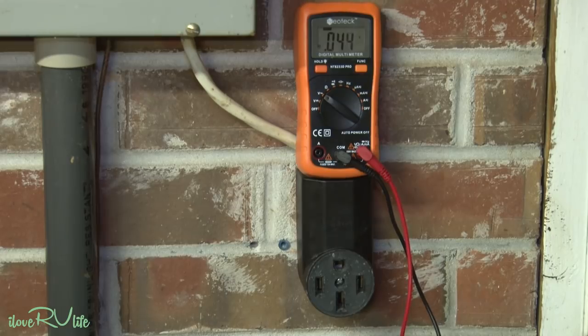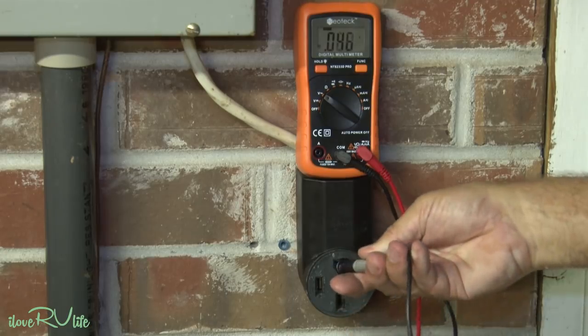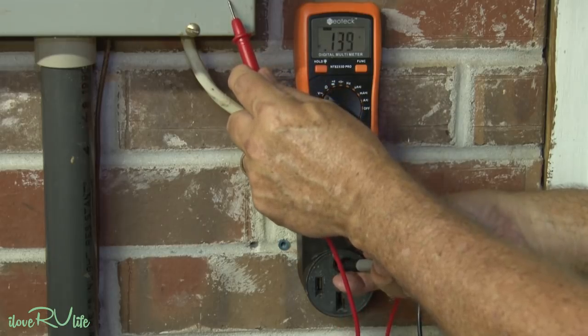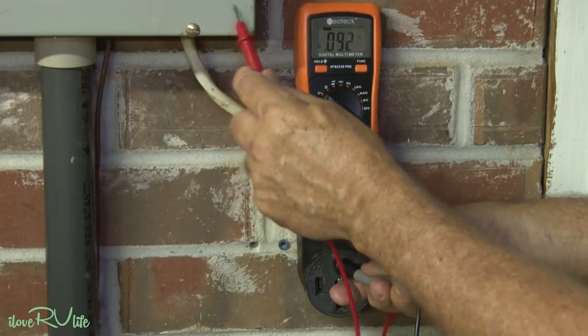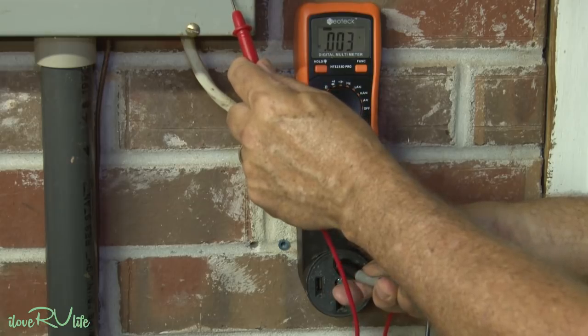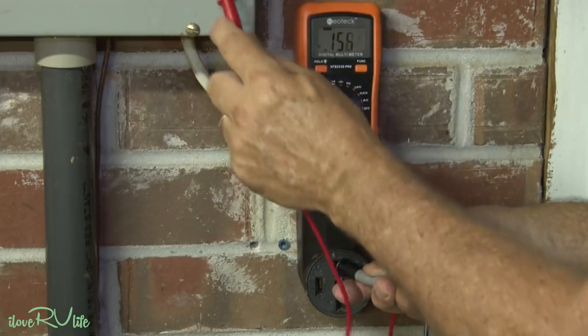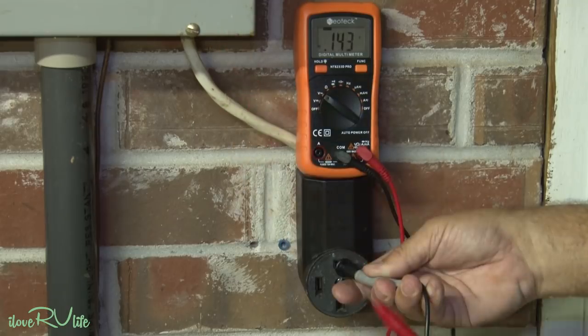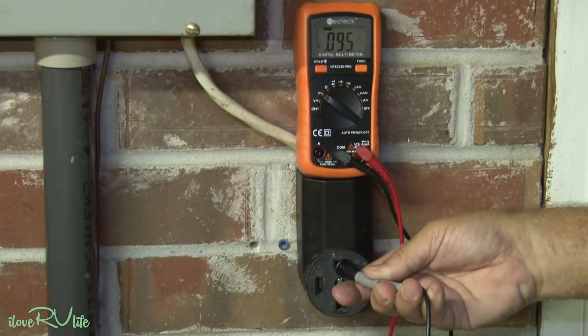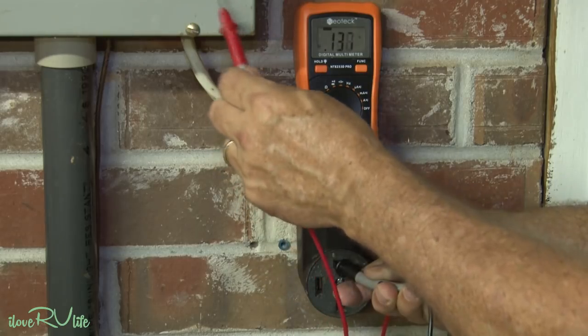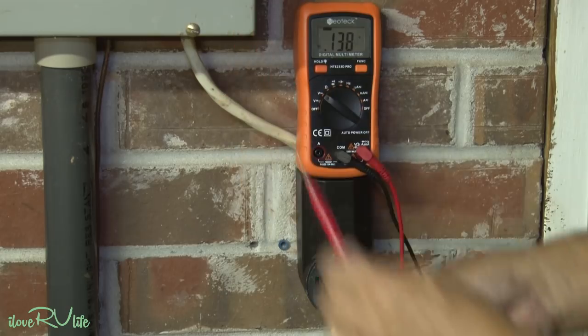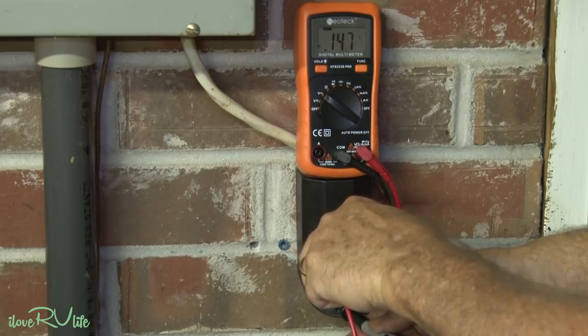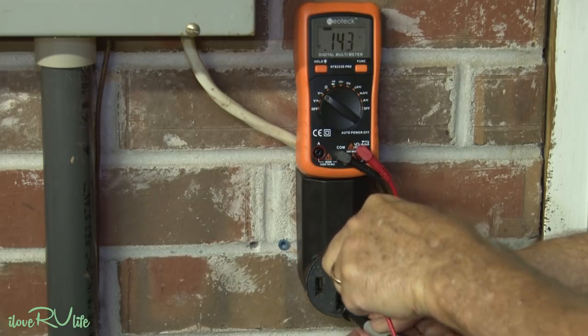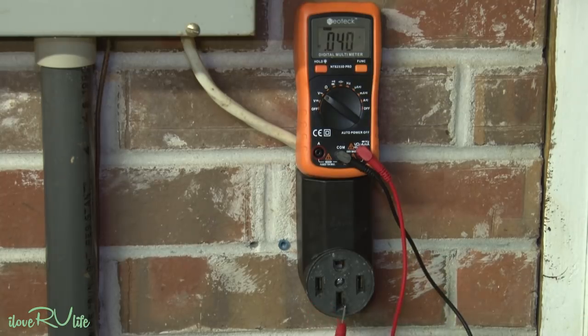The next thing I want to do is test my ground, touching it to the case up here to make sure I don't have any voltage. If I see voltage coming off of this, then I know I've got what they refer to as a hot neutral. There's a lot of discussion right now about hot skin on your RV. You can also go down to your neutral and touch it to the ground, and you should not be reading anything there either. That would also indicate these were reversed.